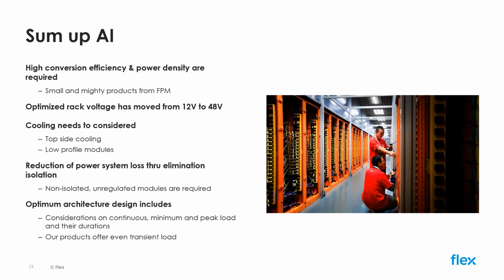Of course, with that increase in power density and power usage, cooling is a massive issue. Direct-to-chip cooling is very common right now. Moving forward, things like immersion cooling are gaining further ground — there are some issues with regard to environmental sustainability on the two-phase side, but on single-phase it's still very much in discussion. So our modules have to be optimized for top-side cooling, for example, or bottom-side cooling for low-profile rear board-mounted modules.